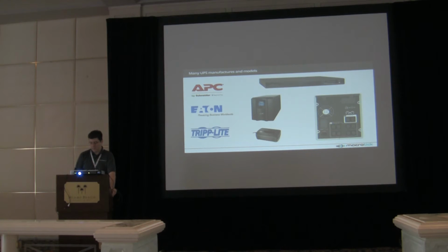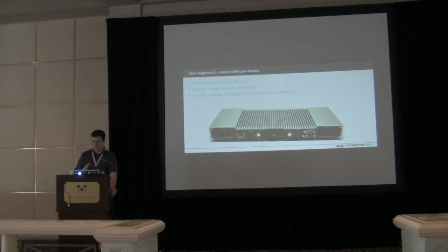devices, because if you look at these 10 devices, we find out that often customers are connecting non-critical devices on UPS. So out of these 10 devices, it might be only 5 that are critical, but they end up connecting all of them because they want to protect from power surges, which in this case will obviously shorten the life of the battery if you end up powering devices that are not really critical. So by doing it per device, you allocate how long you want that device up and running, and obviously the battery size as well as the load of the device varies how long this device will be up and running.